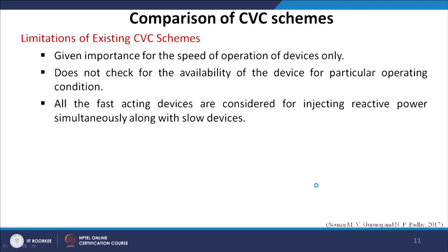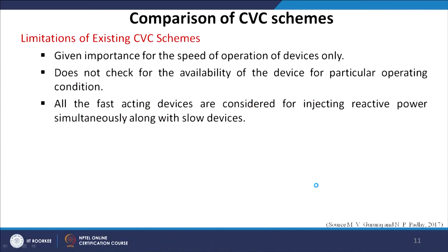The current limitations of the existing CVC scheme: it gives importance only to the speed of operation of devices, and does not check for the availability of devices for particular operating conditions. All fast-acting devices are considered for injecting reactive power simultaneously along with slow devices. As a result, the fast-acting devices are always regularly participating in injecting reactive power, and the slow devices unfortunately may not be able to contribute in time.